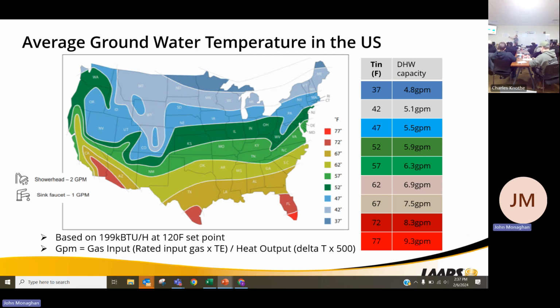But right around in our area, we're going to fall in that bluish area. 47-degree average water temperature. We're going to be about 5.5 gallons a minute out of the product. Most of our shower heads are 2 gallons a minute. Most of our sink faucets are 1 gallon a minute. Go ahead and size it for it.